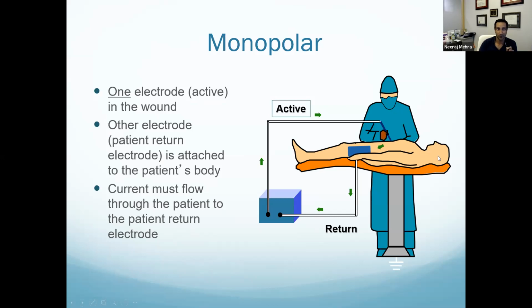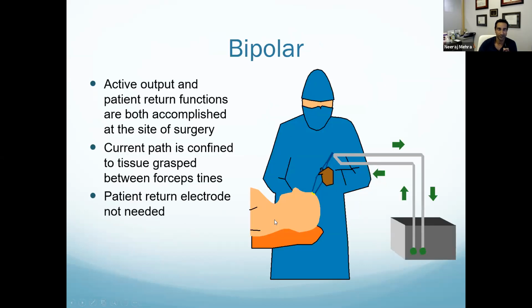So this is our monopolar circuit. A monopolar circuit is where we have our electrosurgical unit and our active electrode, so that's the term that we refer to. The active electrode is the one that's active on the patient. Energy flows through the patient and comes back through our return electrode, and then back to our electrosurgical generator.